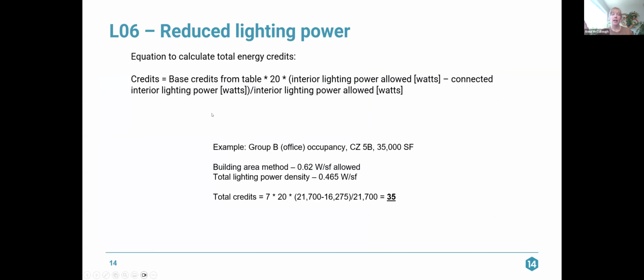So there is an equation to calculate the total energy credits that you can receive. Your credits are going to equal the base credits from the table times 20 times the maximum interior lighting power allowed from your COMcheck, minus the connected interior lighting power provided from your COMcheck, divided by the interior lighting power allowed. So it's just like our percentage savings, right?